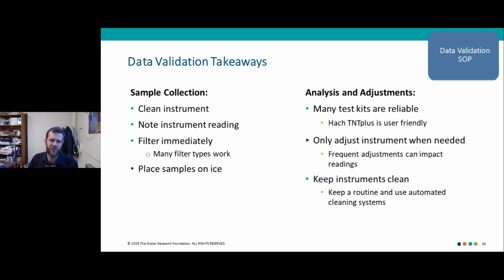The big takeaways from this part of the study were that for our SOP for sample collection, we recommend that you clean the instrument, put it back in the mixed liquor, for example, let it sit for a little bit, note your instrument reading, collect your sample right next to where the instrument or sensor is located, and filter that sample immediately.